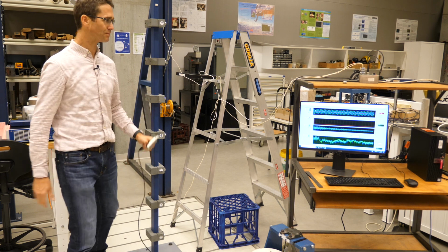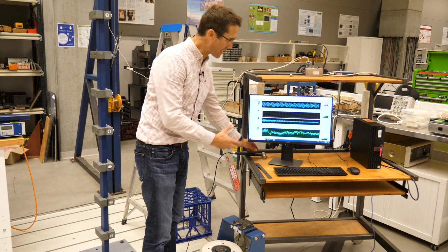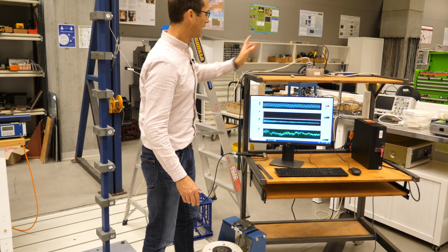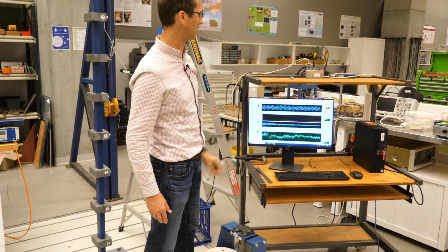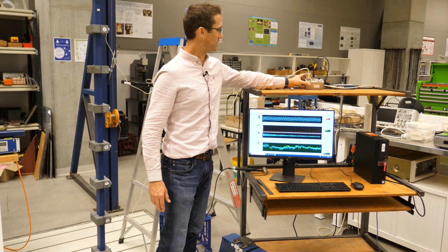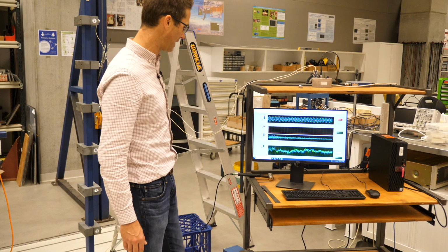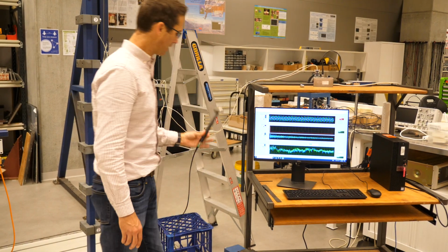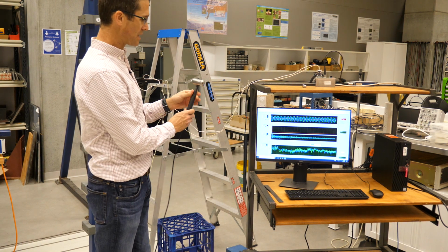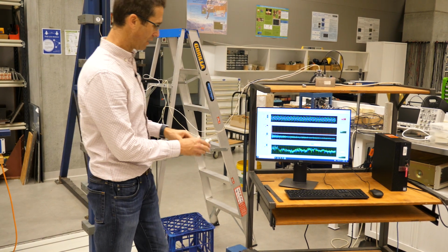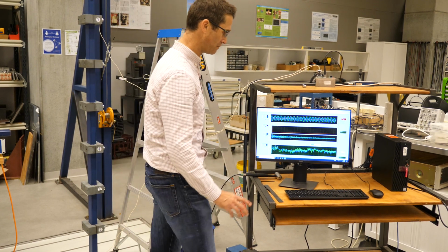I have a bespoke acquisition system over here that's built on a National Instruments LabVIEW solution. I have hardware here, a data acquisition system, USB connected to the acquisition system here. My 2 response transducers are powered by this power supply sitting up on the top there. My impact hammer is an IEPE based sensor. That device is being offered signal conditioning by the National Instruments acquisition system.